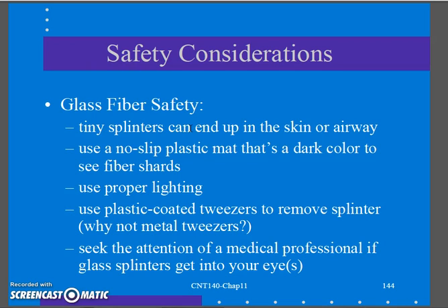But I have to be very careful of those little, as I'm cleaving the fiber, those little stubs of glass that come off, because that could be like a splinter in your finger, and a clear glass splinter in your finger is very dangerous because you cannot see it, and you can't just grab a hold of it and pull it out because you can't see the thing. So they talk all about when you're dealing with fiber, safety glasses for your eyes, using those special tools that catch the cleaved fibers off, and then using special tools that would handle the fiber correctly. And if I do have any kind of splinter in my finger, there is special tweezers I use to pull it out. Plastic coated ones, not metal ones. Metal ones will just shatter it.